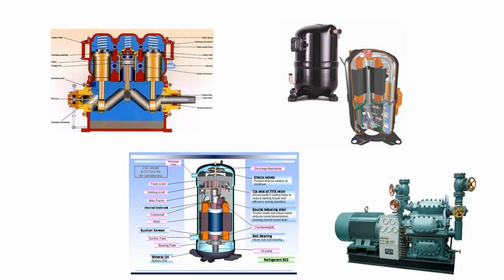That's serviceable. You can open up the compressors. That's actually an ammonia system. But the motor is separate from the compressor versus the hermetic there at top. If that motor goes out, you've got to replace the whole compressor. So in one case, if your motor goes out, you just replace the motor on the semi-hermetic or the open drive, and you can actually work on the compressor by itself. But in the hermetic versions, you have to replace the whole thing if something goes wrong.